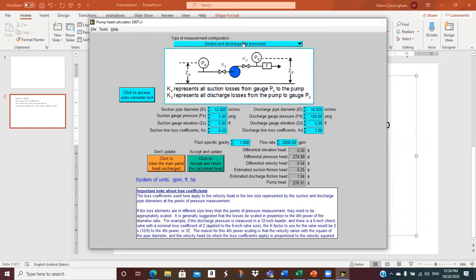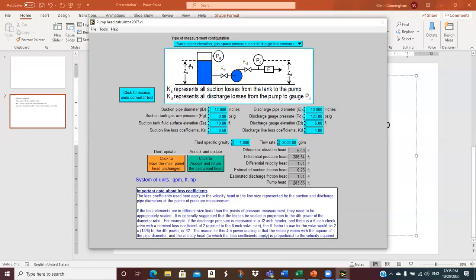So that's one geometry. And then oftentimes in a plant, you see a situation like this, where you're pumping out of a large tank. This would be called a suction tank. We would maintain some elevation in the suction tank, a number of feet above this datum. Sometimes you don't have a suction gauge, so we calculate any pressure above atmosphere and this elevation of water to calculate the pressure at the suction of the pump. So you use this if you don't have a suction gauge, or you have to measure or start guessing.